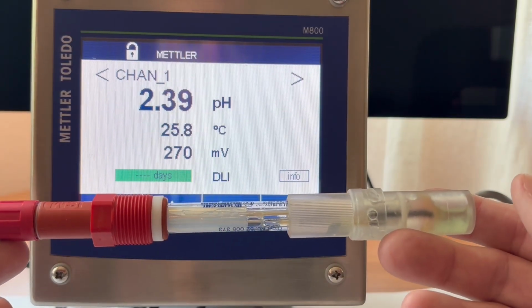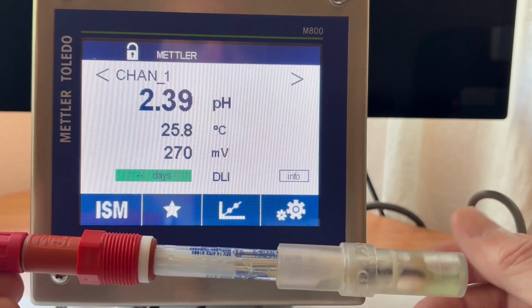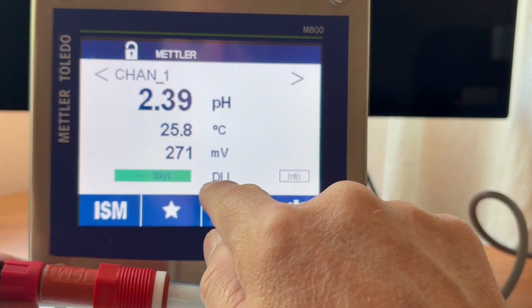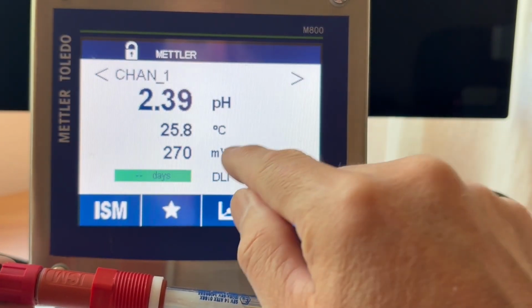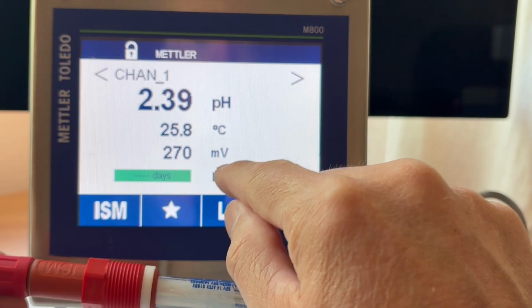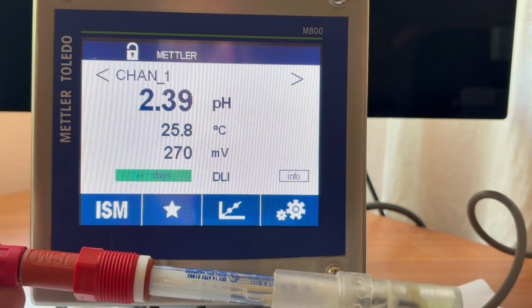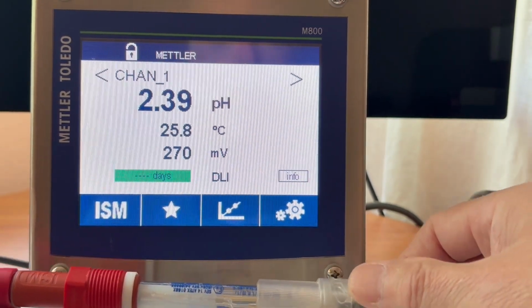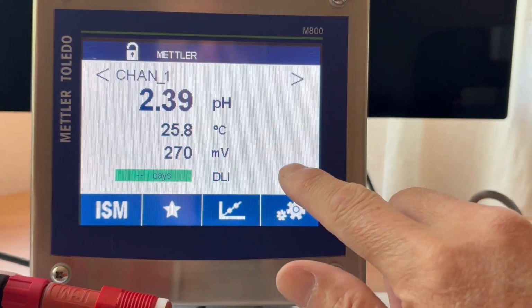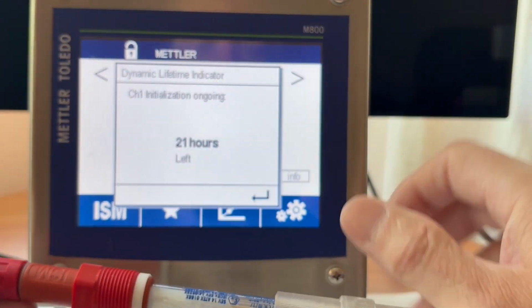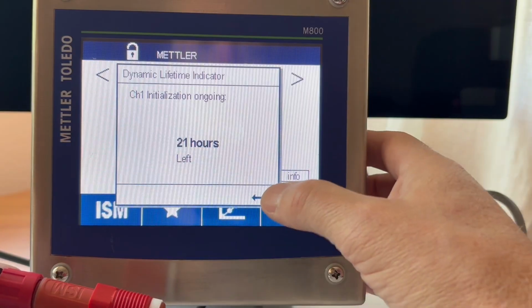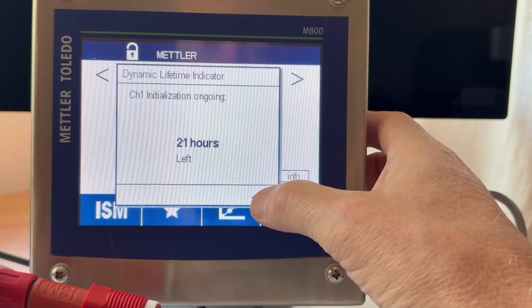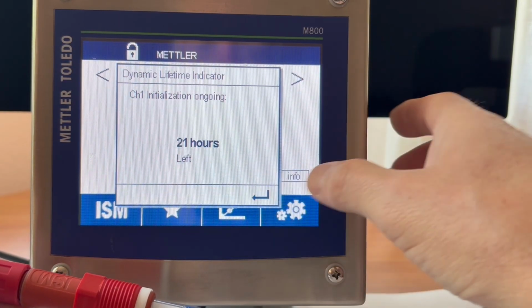Here's a sensor connected. It's a relatively new sensor that's connected. My DLI, my dynamic lifetime indicator, this is calculating how many days of life is left on the sensor. When you attach a new sensor, it takes 24 hours for that to occur. We can actually have that tell us that we have 21 more hours before my DLI algorithm is going to give me the calculated number of days that the sensor has.